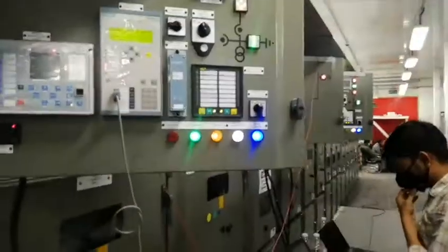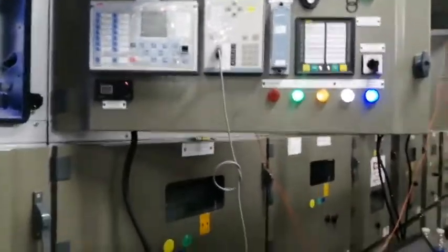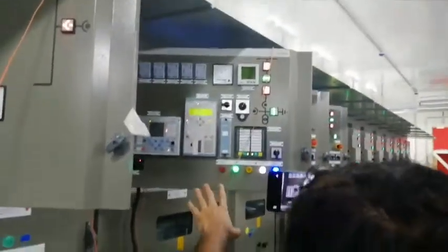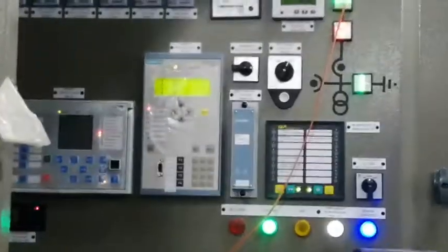I would again reiterate that we tested this after configuring the other relay as a 132 kV relay. This is the other panel. In order to simulate the 132 kV side, because in the e-house we don't have the 132 kV system, we configured this relay for the 132 kV side, and we checked the interface between this relay and the relay installed in that incomer panel.